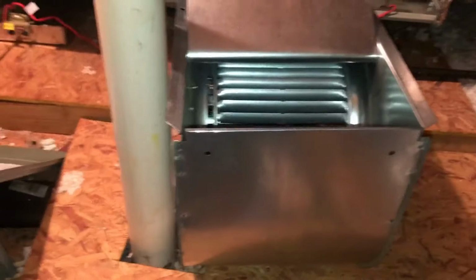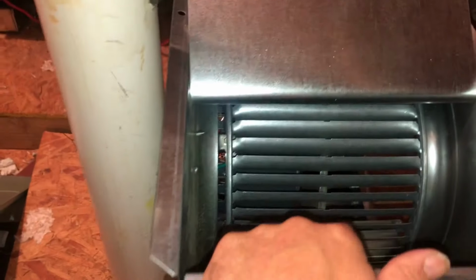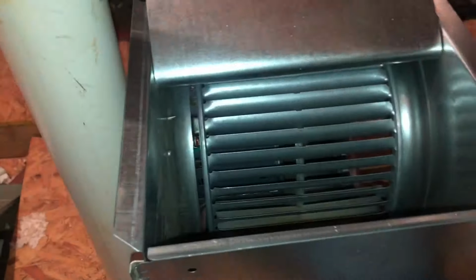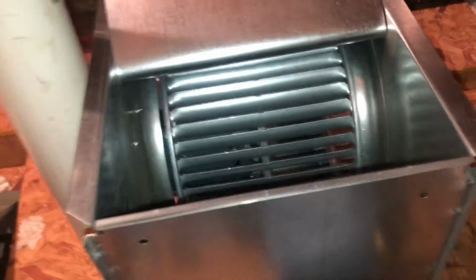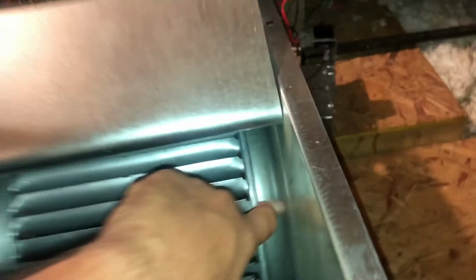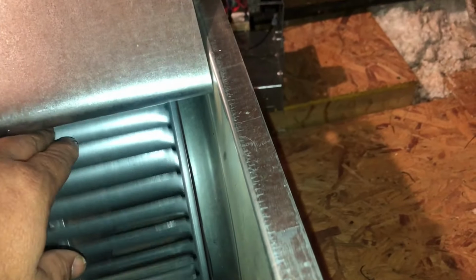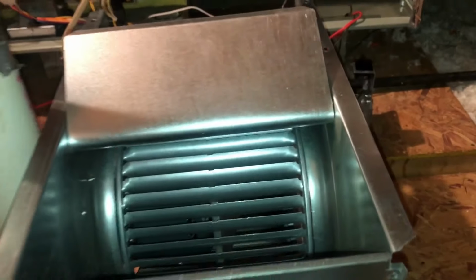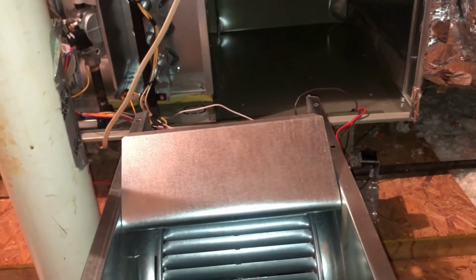All right, so I'm not going to beat on it anymore. I'm just not comfortable with that. I would rather have this thing beyond the center, because the motor's on the top, and as the motor wears and shaft play, it will eventually be down again. So I'm not at all really thrilled about it, but I'm not going to hit it anymore. I just don't think I'm helping the motor any doing that.